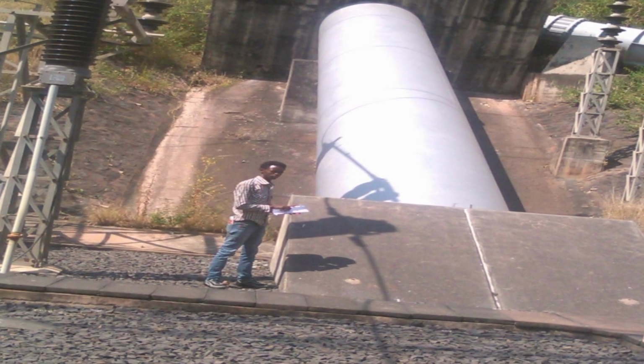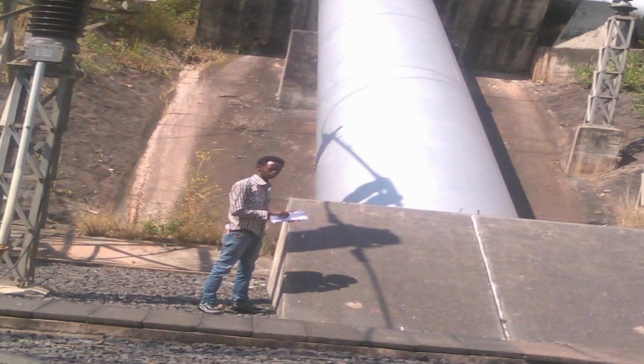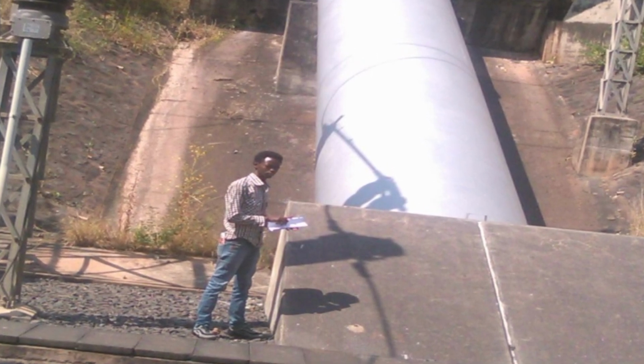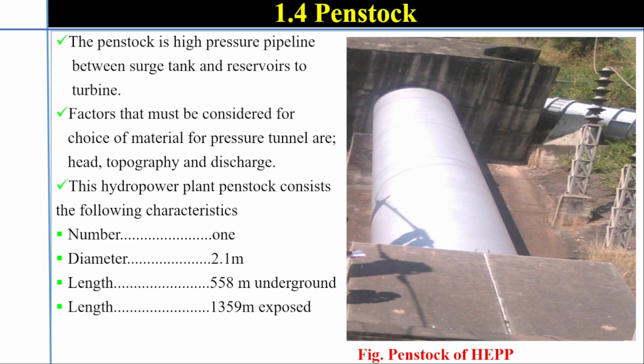1.4 Penstock. The penstock is a high pressure pipeline carrying water from the surge tank and reservoir to the turbine. Factors that must be considered for choice of material for pressure tunnels are head, topography, and discharge. This hydropower plant penstock has the following characteristics: 2.1 meter diameter, 558 meters underground, buried penstock, and 1359 meters exposed on the Earth's surface. As you can see, this picture is the penstock surrounding the powerhouse.